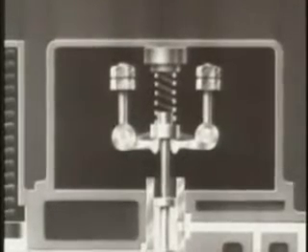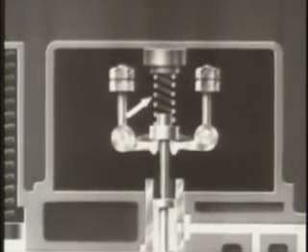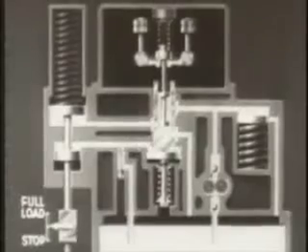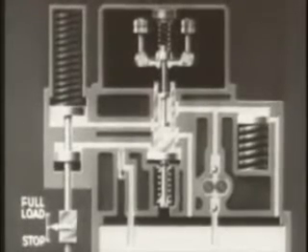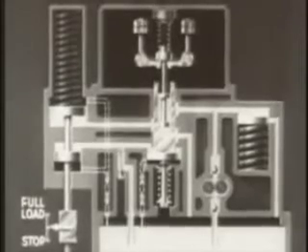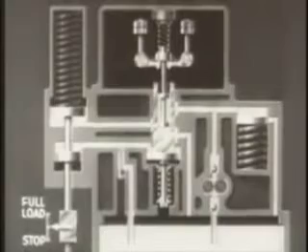The governed speed of the engine is set by changing the tension of the speed-adjusting spring. The pressure of this spring determines the engine speed necessary for the flyweights to maintain their central position. Oil, allowed to leak past the various plungers for lubrication purposes, is drained into the governor oil sump. These are the basic elements of this type of regulating governor. In actual operation, the events which we have seen step by step take place almost simultaneously.